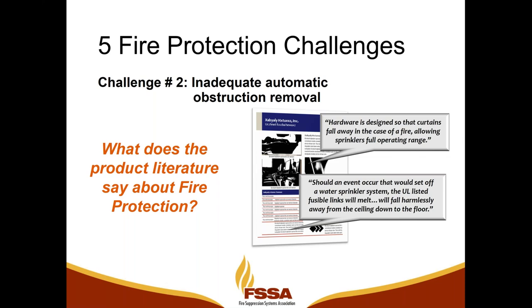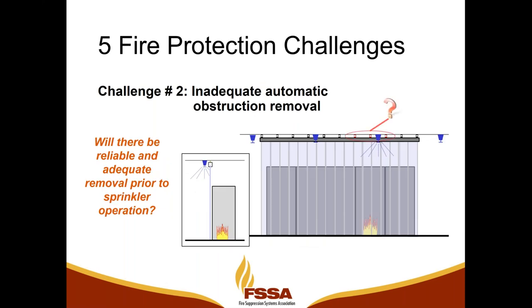The hardware is designed so that the curtains fall away in the case of a fire, allowing sprinklers full operating range. And the other quote: should an event occur that would set off a water sprinkler system, the UL listed fusible links will melt and will fall harmlessly away from the ceiling down to the floor. That's really the misnomer. Yes, they are UL listed links, but in this application it can be a real problem. Think about whether those fusible links will actually allow that curtain to fall away.